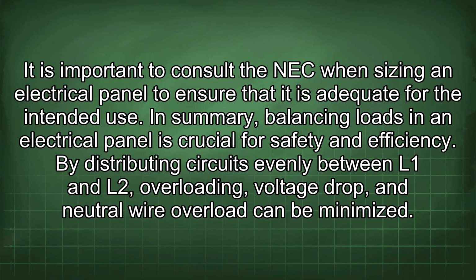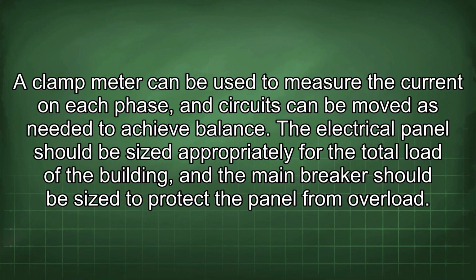It is important to consult the NEC when sizing an electrical panel to ensure that it is adequate for the intended use. In summary, balancing loads in an electrical panel is crucial for safety and efficiency. By distributing circuits evenly between L1 and L2, overloading, voltage drop, and neutral wire overload can be minimized.